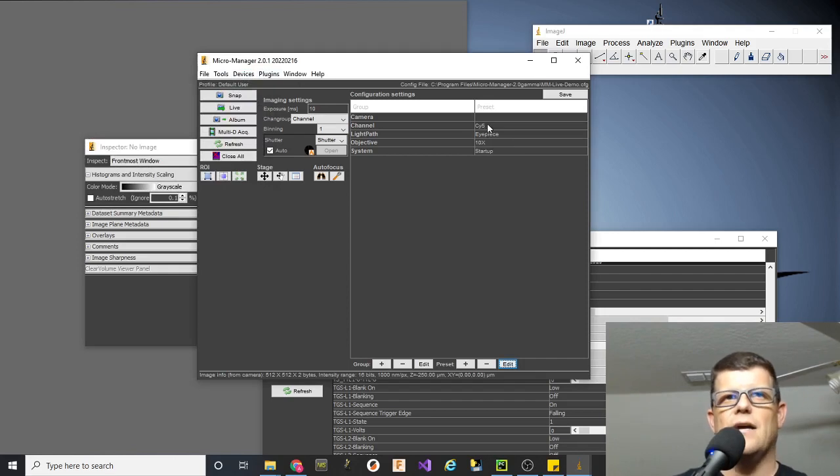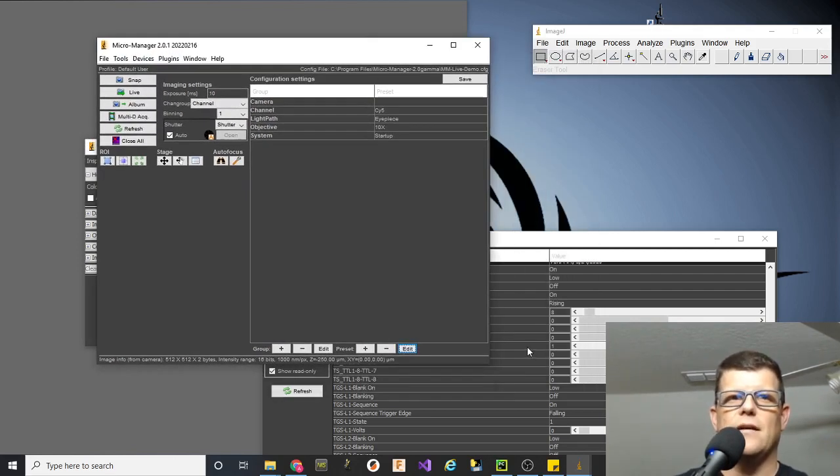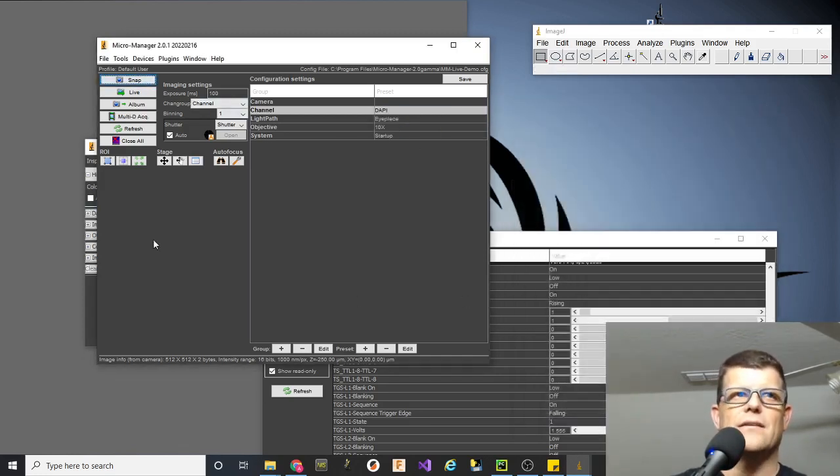But in this case now, Cy5 is set up so that TTL line output 4 is active, and my power level for my appropriate DAC is going to be brought up. So if I want to switch my channel, Cy5, I snap my image, go back to DAPI, snap an image, and my settings are going to flip-flop as the system acquires. And that'll work in multi-D, and the shutter will control the output for being on or off overall.